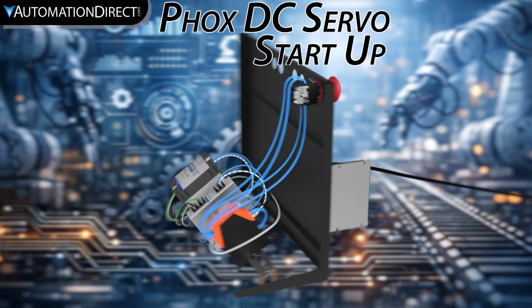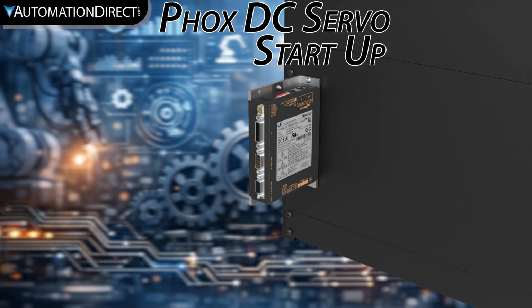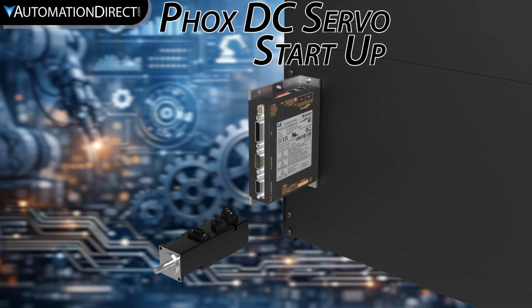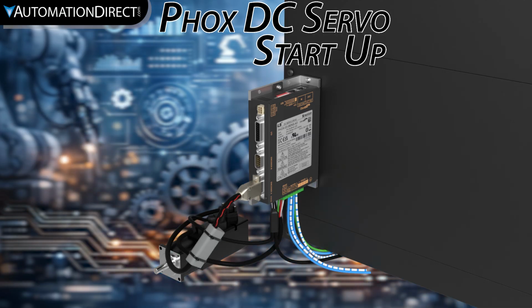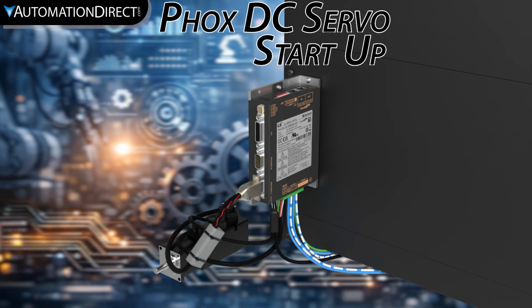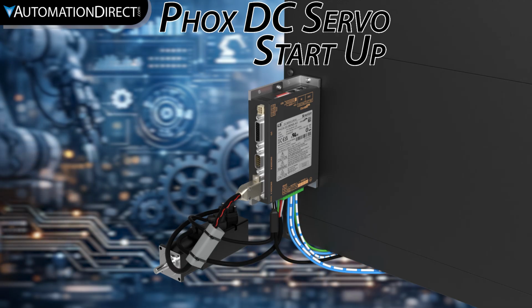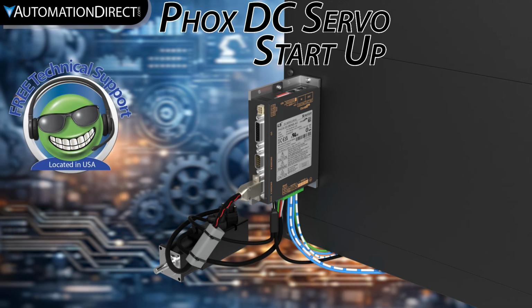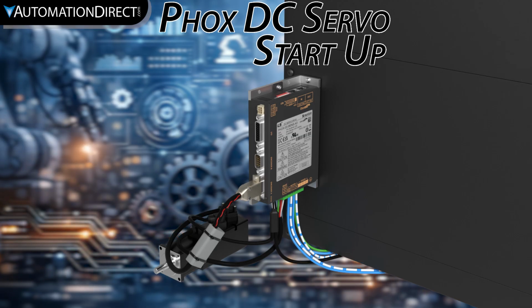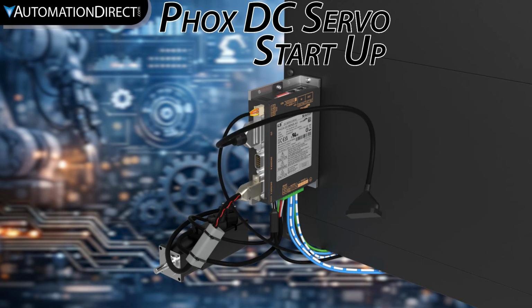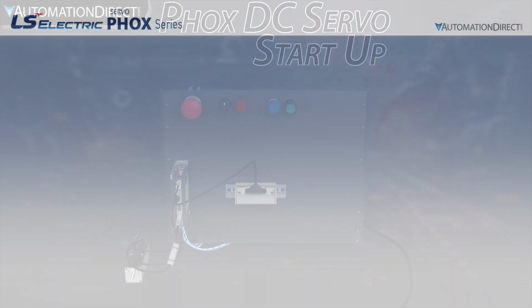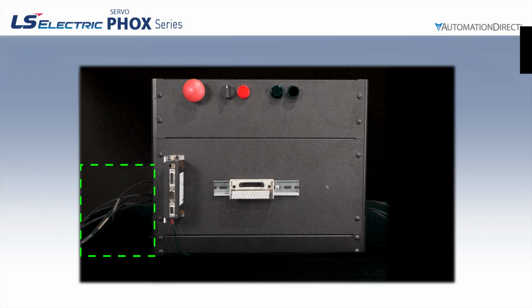For this setup, we're using the 3 amp Phox DC drive, a 100 watt braked motor, and the corresponding encoder, brake, and power cables. While the drive supports third-party motors, using motors available from AutomationDirect.com enables full access to our free award-winning technical support and online resources. We're also using an STO cable, an I/O cable, and a feed-through terminal block to allow push-button control. We have already installed all our incoming feed power, wiring, and terminal blocks, and we've mounted the drive to our test plate using 2 self-tapping screws. We also have a length of DIN rail mounted and ready for the drive's I/O feed-through terminal block.